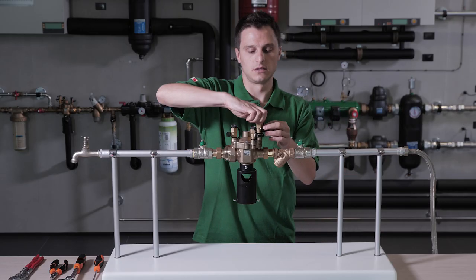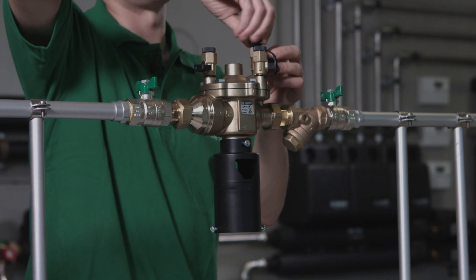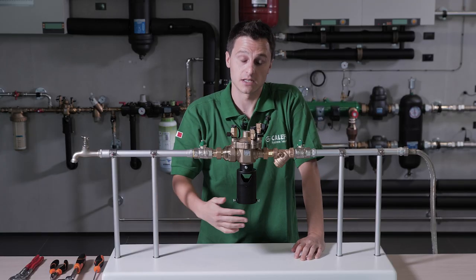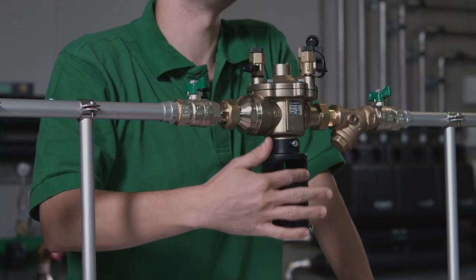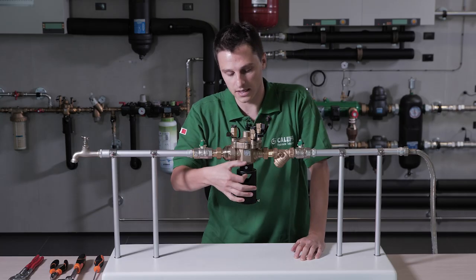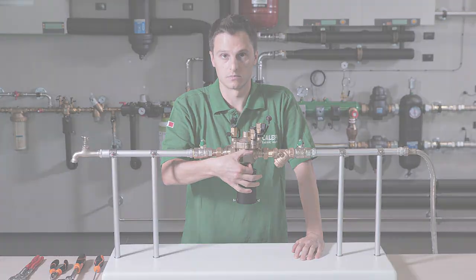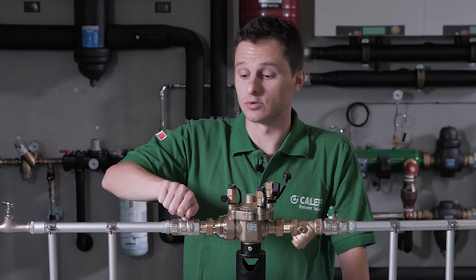and open the upstream chamber pressure tap. If there is absence of discharge flow or the discharge flow is too low, it means that the opening mechanism and the obturator are blocked. Let's open again the downstream shutoff valve.